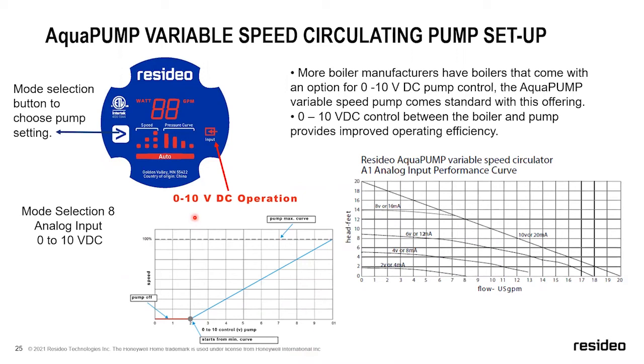There are third-party controllers that allow you, I mean, we even make some with our T775s, that allow you to control and modulate the flow rate around the system side. I will give you a piece of opinion, and everybody knows what opinions are worth, but I'm not personally a fan of using third-party controllers to modulate variable speed pumps residentially on the system side. I've seen it. We used to make some controls and we discontinued them that did it. More times than not, they weren't programmed correctly, which led to more problems than they helped.